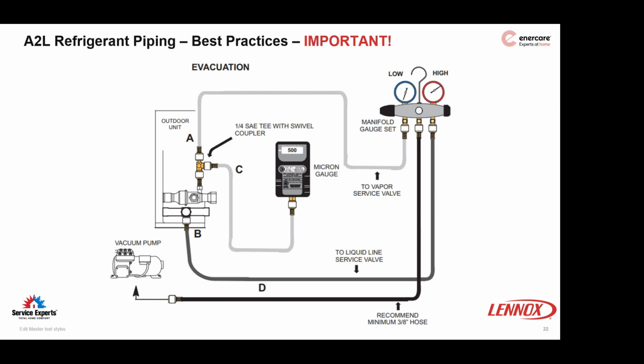Some manufacturers do demand a lower level of evacuation. None that I've currently read, at least not with the new stuff. Anything below 500 seems to be the sweet spot for Lennox, Carrier, and the Goodman product line. But in those instances, please follow the manufacturer's directions if they are more stringent.